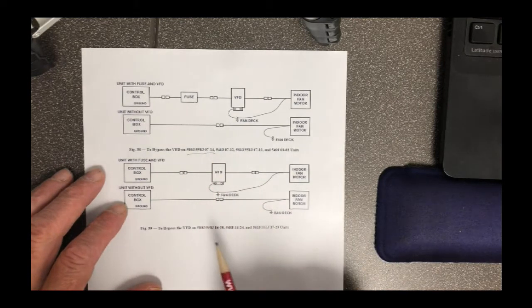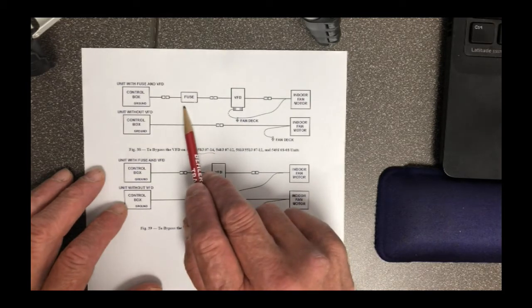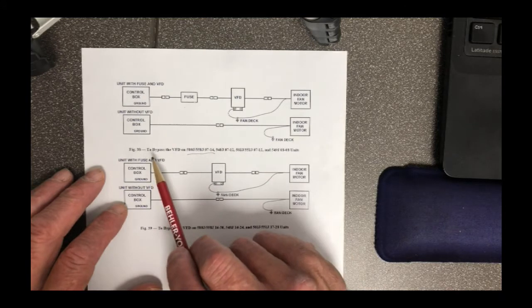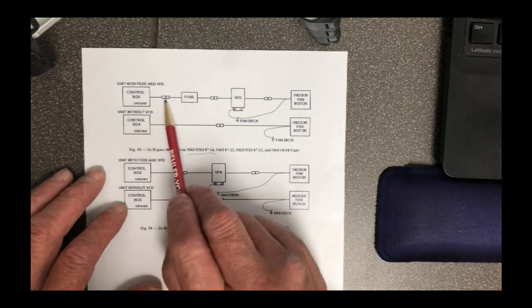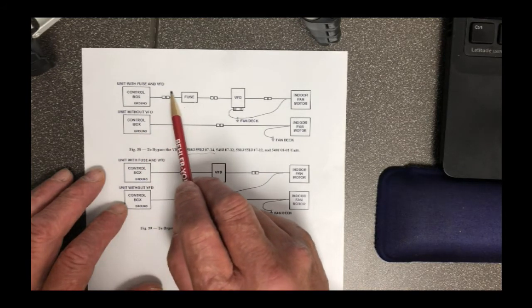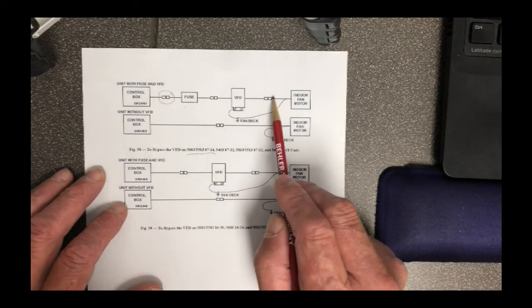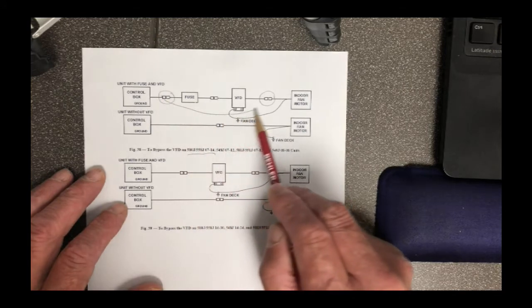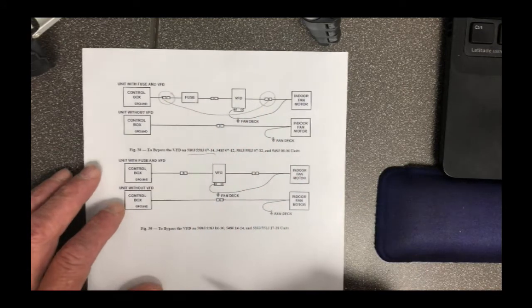One thing to know about how this works: on the smaller units, the 580J 07 through 14, there's a fuse box that's in line with the drive. So I want to make sure I take this fuse box out as well. You can see there are spade connectors here. For my control box, I'm going to unplug here, unplug from the motor, and plug those directly in. I have to get those fuses out of this circuit.